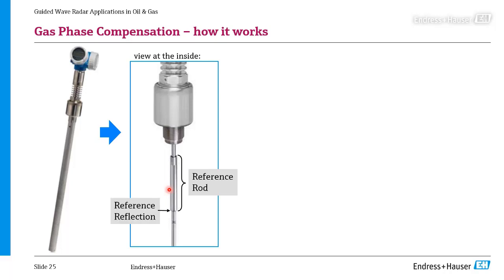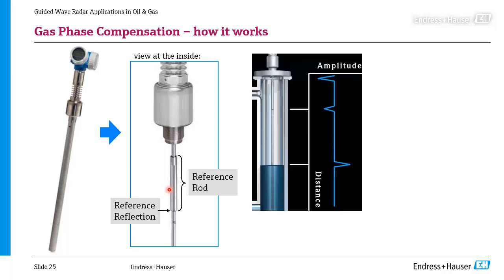This reference reflection is created here, as you see in this example: the in-coupling signal, then this small signal we call a negative signal because it points in this direction. It shows exactly where the end of the reference rod is, and we know exactly where that has to end, so we have a clear picture. Under normal conditions, with no steam or gas phase, the level is measured correctly - we see the right level.